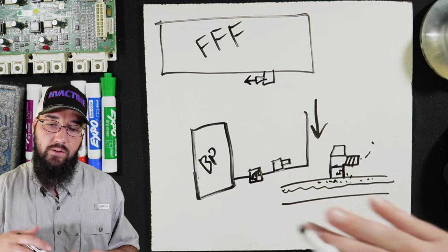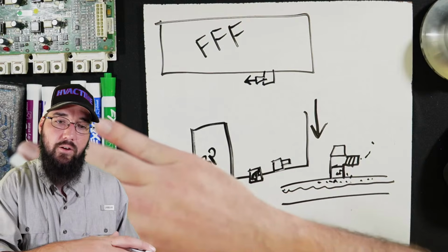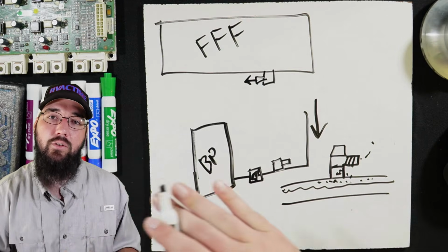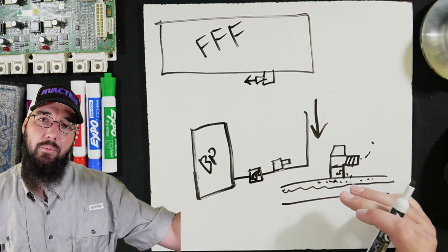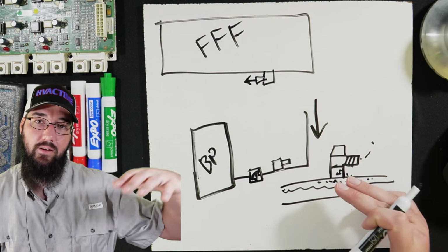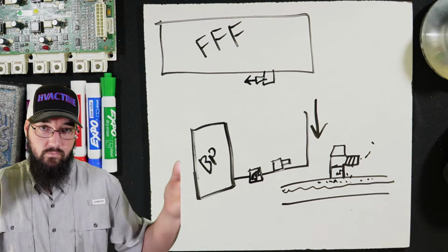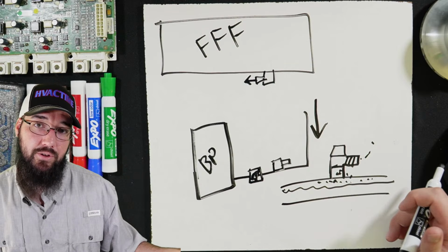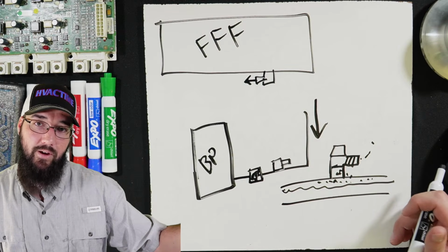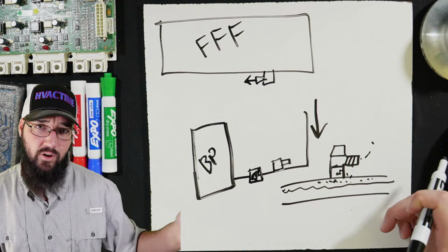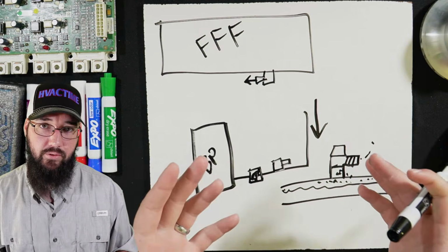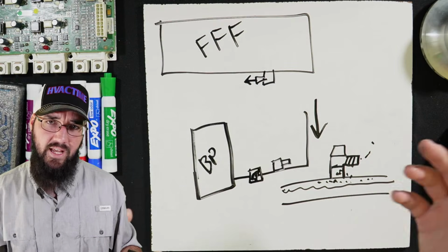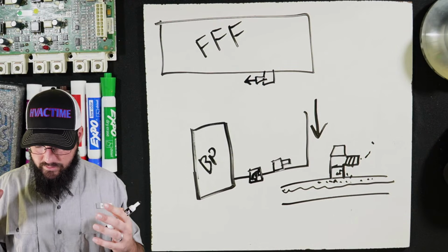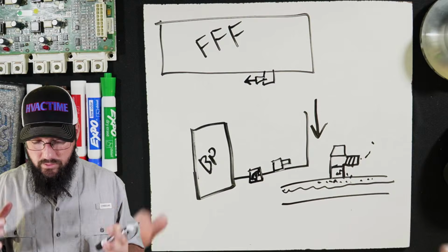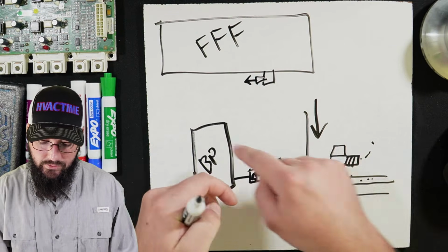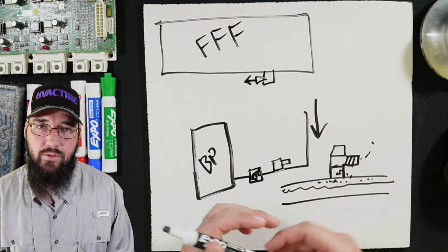So on many of those machines, the two-phase line comes down and around, and then angles up into the evaporator. It is on the upper angle of that line coming through. Not to mention it's a pump down machine to begin with, so that whole evaporator is empty if they pump down correctly in the first place and it hasn't migrated. So, long story short, in this scenario, it's not worth your time.